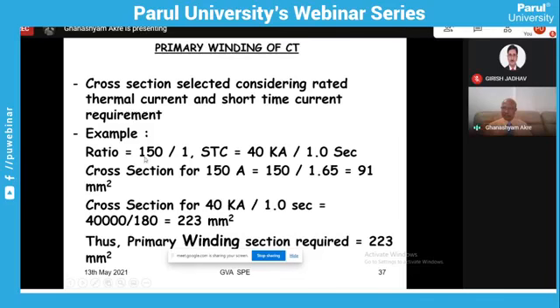Suppose I have selected a ratio of 150/1 and the STC is 40 kiloamperes for 1 second. In that case, what happens? The cross section for 150 amperes will be 150 amperes divided by 1.65 amps per square millimeter, because this normally works at a low current density. So this will require 91 square millimeters of primary section. But in the second case, it also has to suffice for 40 kiloamperes for 1 second. In that case, 40 kiloamperes divided by 180 amps per square millimeter, which can be safely taken, will produce 223 square millimeters. So you see, the same transformer, because of its dual rating, instead of 91 we have to utilize 223 square millimeters. Otherwise, the transformer may burn during the short circuit, with the fault current flowing through it.